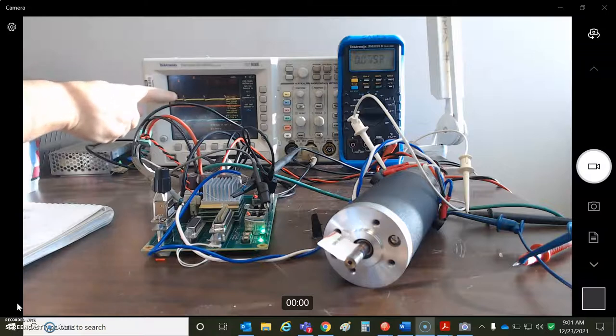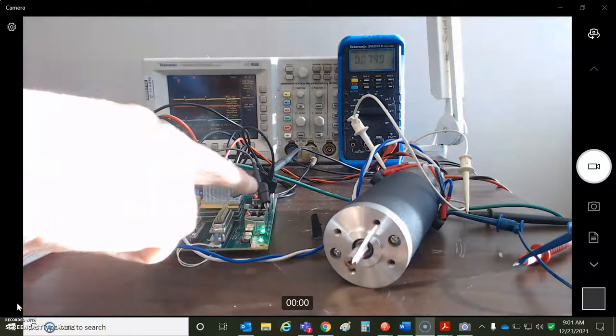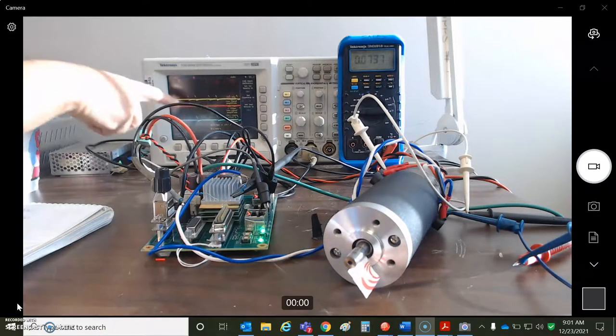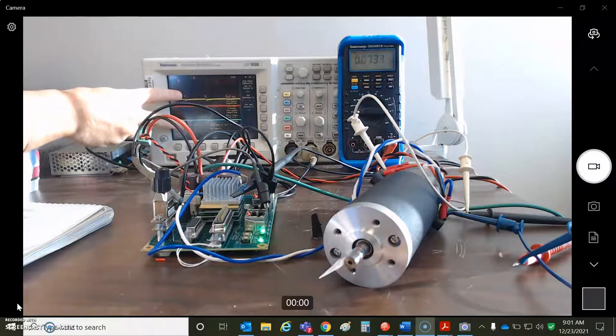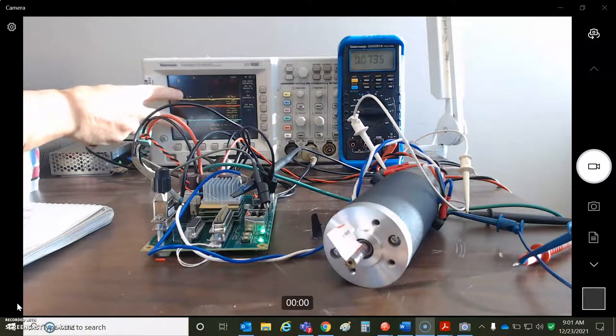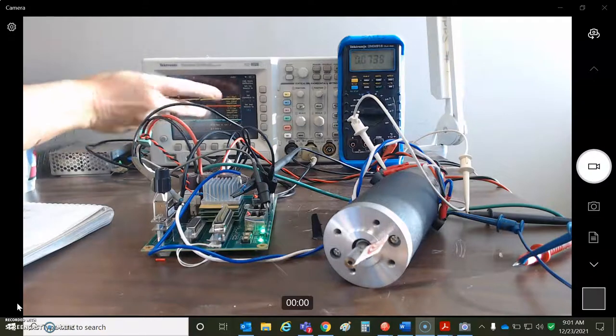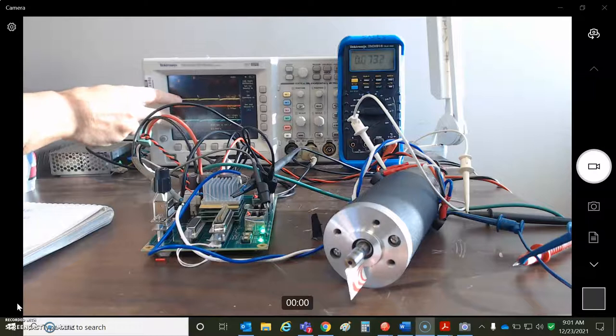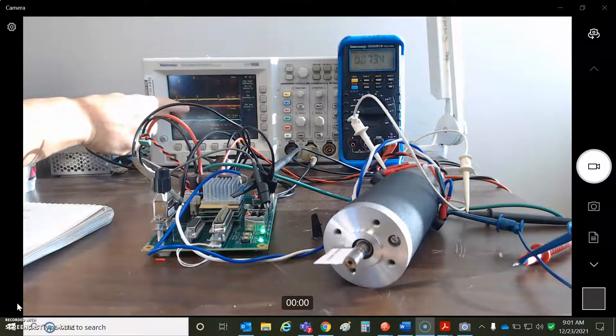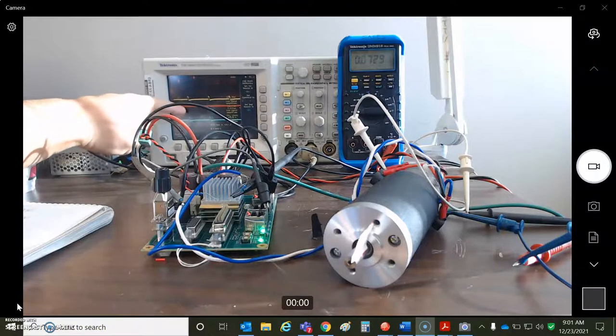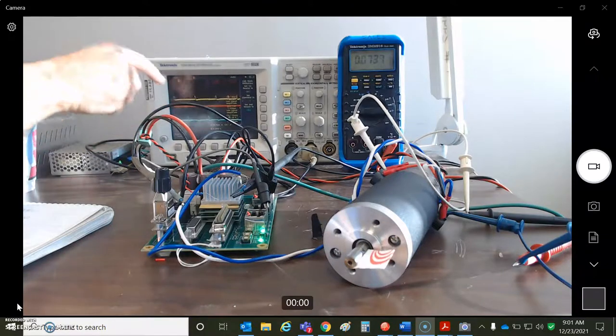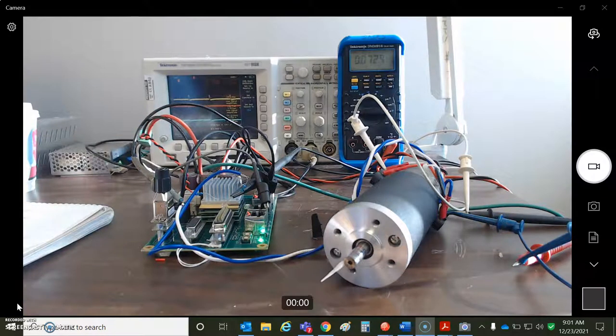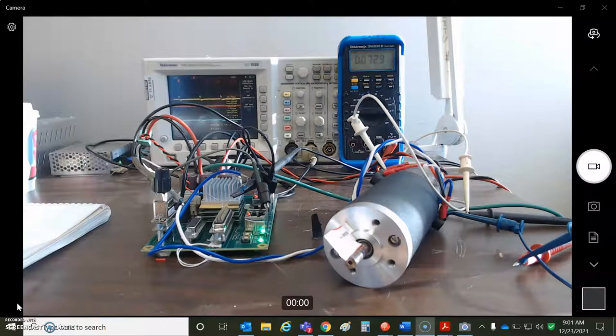I'm measuring also with the scope differentially between the two tachometer outputs before it goes into the drive. So this common mode noise here, there's a little voltage from the offset and the rotation because the tach's measuring as it's rotating. But the common mode noise is rejected by the differential receiver. So you can see sort of add an invert. These two get subtracted. It looks clean, nice and flat. There's a little bit of noise, it's analog, but good signal to noise ratio should keep things humming just fine.